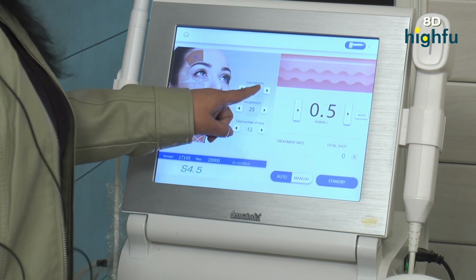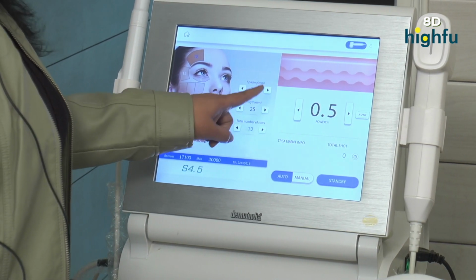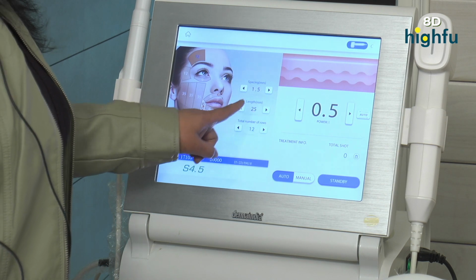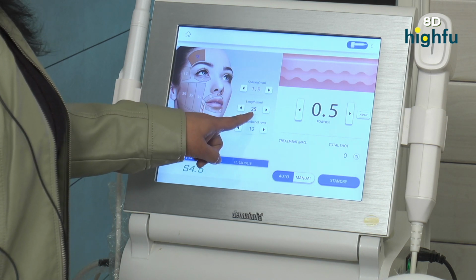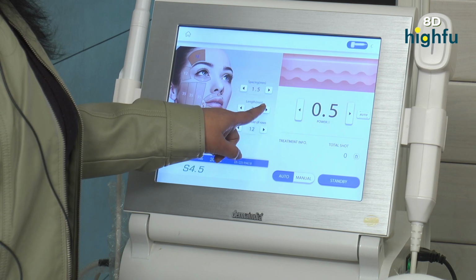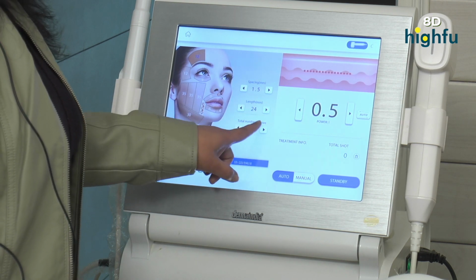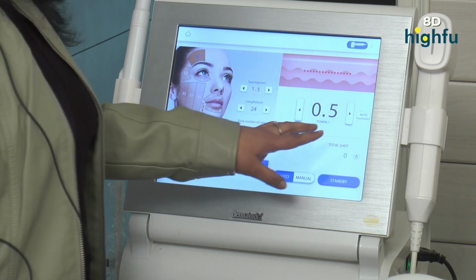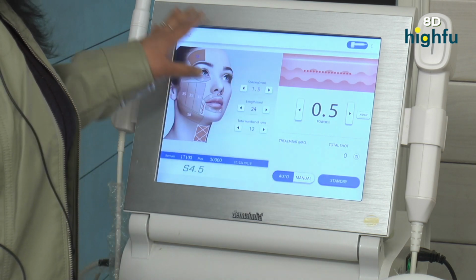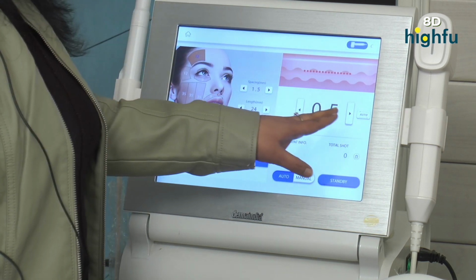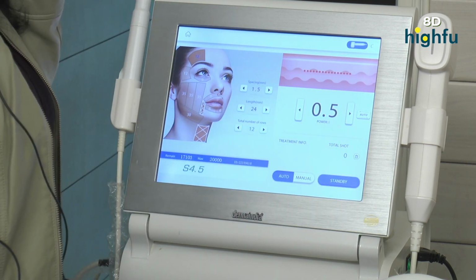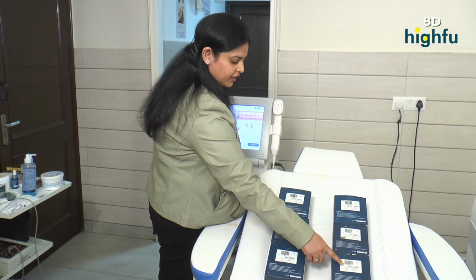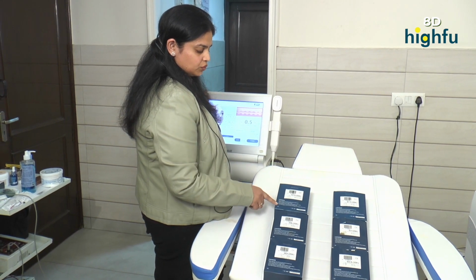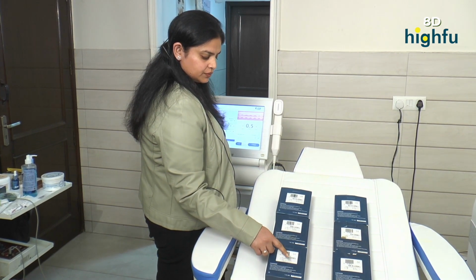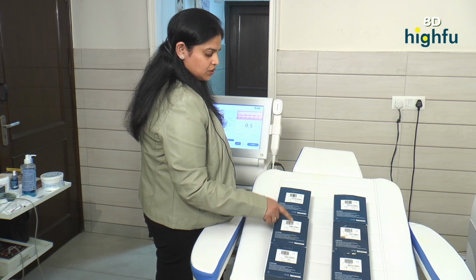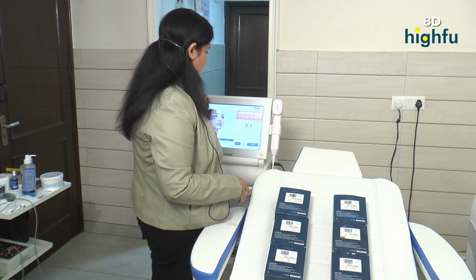We can adjust the spacing, which we usually keep 1.5, or we can increase or decrease according to the patient. We can modulate the length also, is usually 25 mm, or we can increase or decrease the length, and the total number of rows we can also adjust. This is the power which goes from 0.1 to 2 for face, and for body we can go to 3 joules for the body. And in the linear one we have single row 4.5, and for the body we use the multiple row. The depths vary depending upon what area we want to do, 3, 6 or 13. 13 is the maximum we are having in this machine.